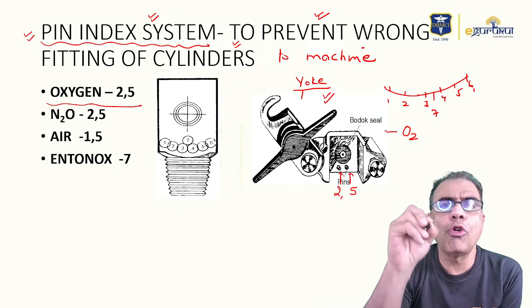At the corresponding place on the cylinder, the holes will also be at the same positions. If this is an oxygen cylinder, the two holes will be at positions 2 and 5. The pin index for nitrous oxide is 3,5. So if this is the yoke of nitrous oxide, the pin positions will be 3 and 5, and the nitrous oxide cylinder will have holes at 3 and 5. Will you be able to fit a nitrous oxide cylinder in place of oxygen? Of course not, because pins and holes will not match. You will not be able to fit one cylinder in place of the other, and you can really prevent a catastrophe.